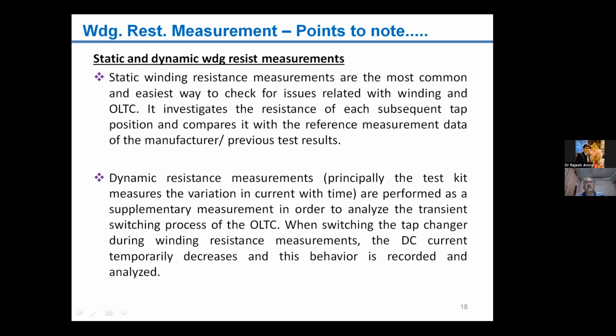Dynamic resistance measurement is when the tap is in operation; during its operation the current variation takes place, and that current variation is recorded with respect to time. By doing this test we come to know if there are some issues in the tap changer during switching, or some issues with the resistance itself. That kind of issue may be checked through the dynamic resistance measurement test. Next.